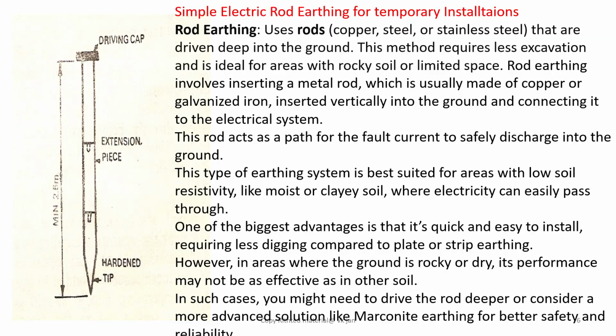Rod earthing involves inserting a metal rod, which is usually made of copper or galvanized iron, vertically into ground and connecting it to the electrical system. This rod acts as a path for fault current to safely discharge into ground. This type of earthing system is best suited for areas with low soil resistivity like moist or clayey soil where electricity can easily pass through. One of the biggest advantages of this is quick and easy to install, requiring less digging compared to plate or strip earthing.